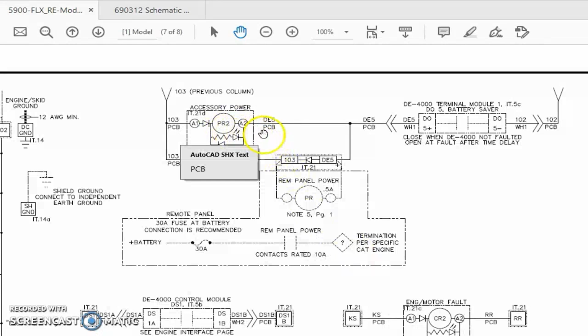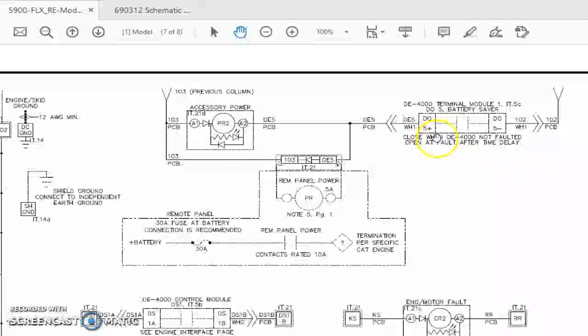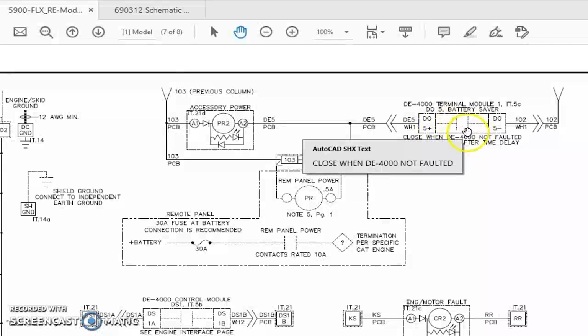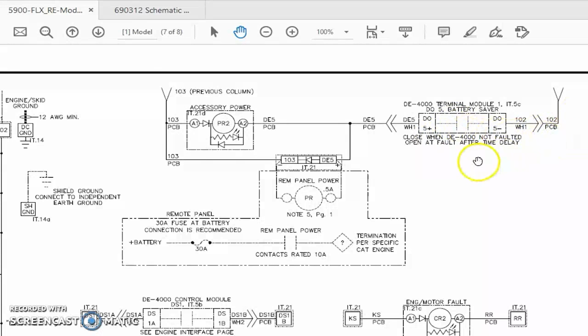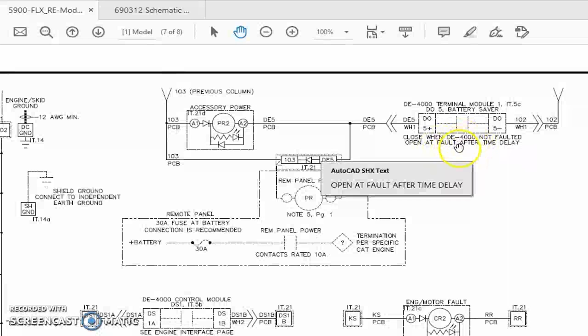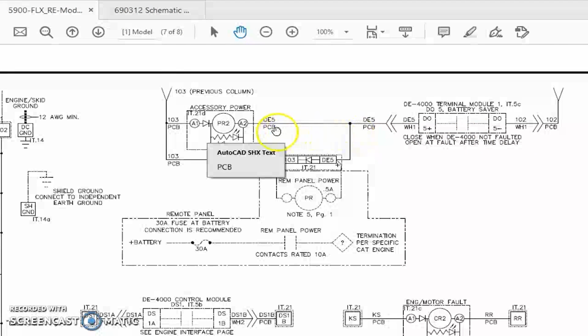On this relay PR2, they're using this wire DE5 from the A2 terminal to turn the relay on and off with a digital output 5 from a DE4000 terminal module. Now, what this does is when this digital output 5 turns on, it closes internal contacts and connects it to ground, and we can have a lot of different control strategies that would do this, but then it would complete a ground path for the PR2 relay, and the PR2 relay would energize and turn on.